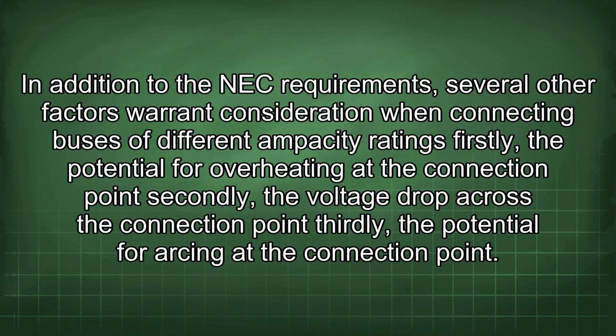In addition to the NEC requirements, several other factors warrant consideration when connecting buses of different ampacity ratings. Firstly, the potential for overheating at the connection point. Secondly, the voltage drop across the connection point. Thirdly, the potential for arcing at the connection point.